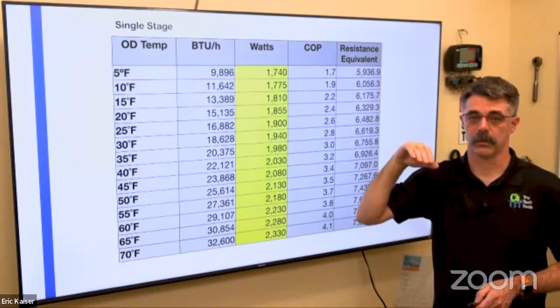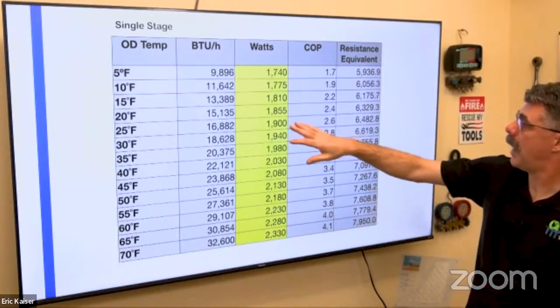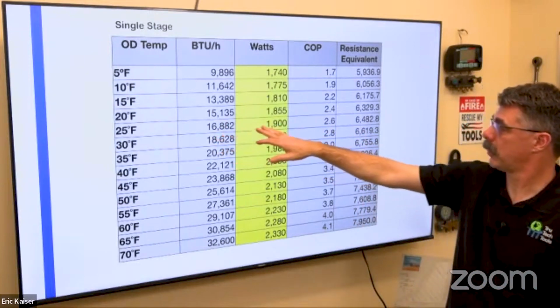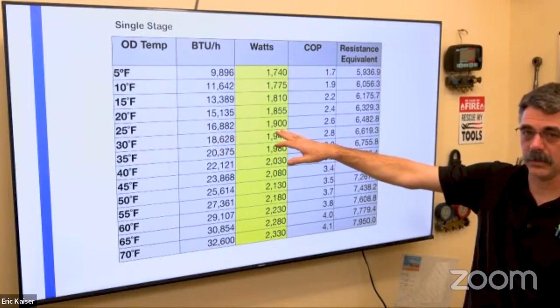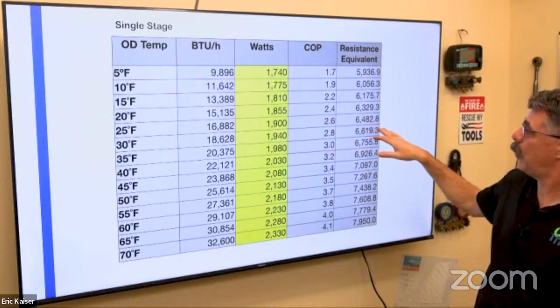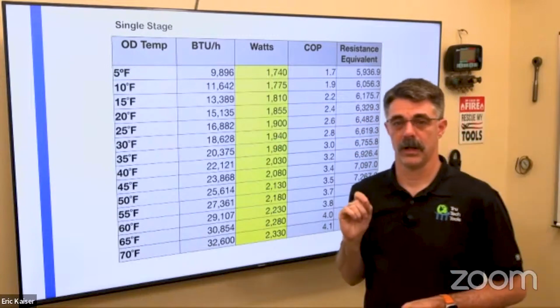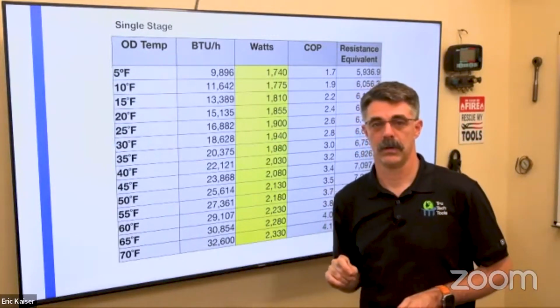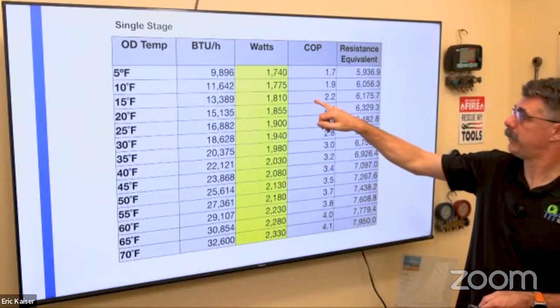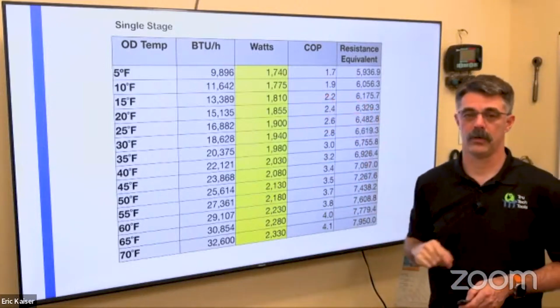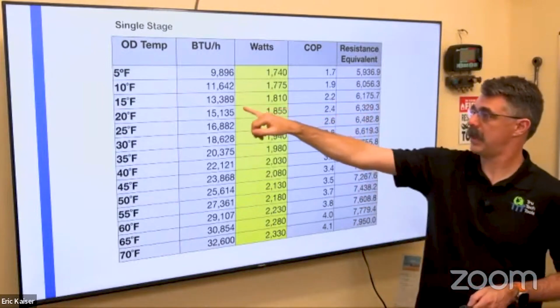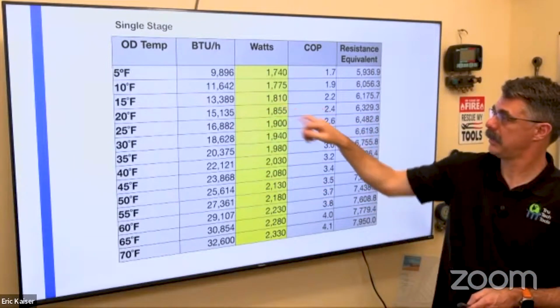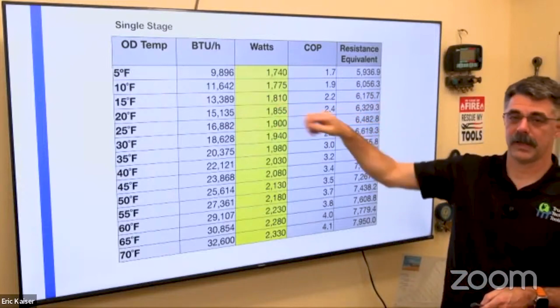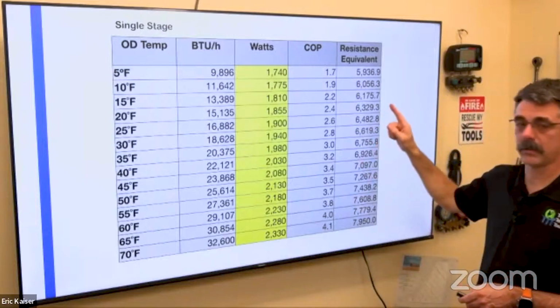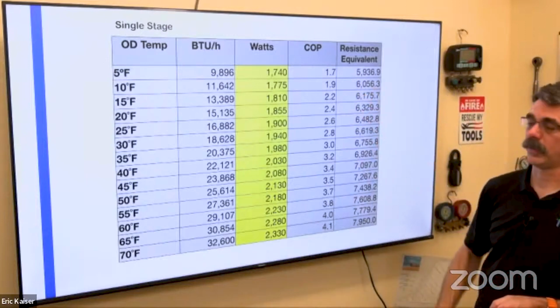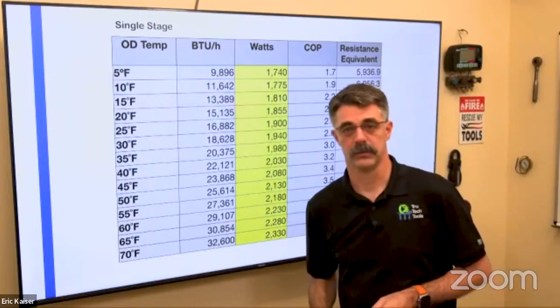Now, COP is coefficient of performance, and that compares how many BTUs I'm delivering versus how many watts I'm putting in to get that work, versus how many watts I would be getting if I was running resistance electric heat. So you can see down here at 15 degrees, I'm still getting 2.2 times the amount of energy out. I'm getting 13,000 BTUs out for 1,800 watts put in. Whereas if I put that same 1,800 watts into electric resistance heat, I would only get a little over 6,000 BTUs out of it instead of 13,000.